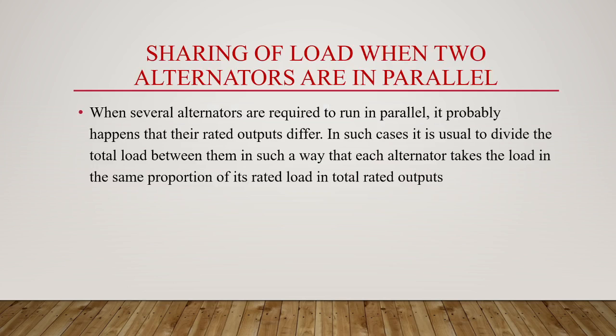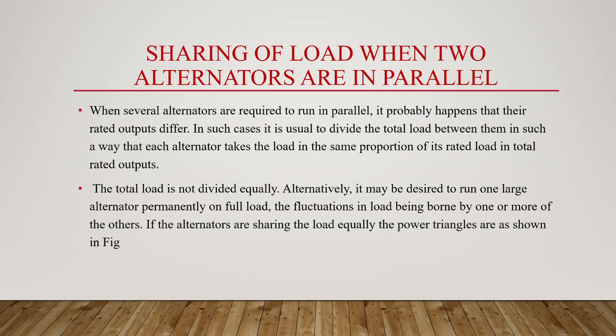So, sharing of load when two alternators are in parallel. When several alternators are required to run in parallel, it will probably happen that their rated outputs will differ. In such cases, it is usual to divide the total load between them in such a way that each alternator takes the load in the same proportion of its rated load in total rated outputs. So the total load is not divided equally. It may be desired to run one large alternator permanently on full load and fluctuations in load being borne by one or more of the alternators.